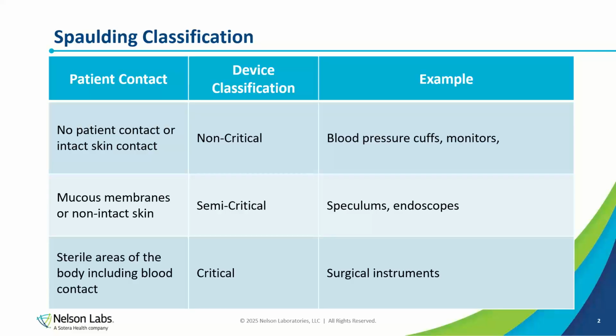Yeah, that's an excellent question. And the answer is it depends on how extensive that design change is, or how different the design of that new device is. It is acceptable to adopt new devices or a design change into a previously completed reprocessing validation, whether that's a cleaning validation or a steam sterilization validation. You just need to assess the devices that were used for these validations, and if they present a greater challenge to the process than the new design or the new device, then you should be able to adopt the device under that previous validation. That's something that I can help with if you would like.